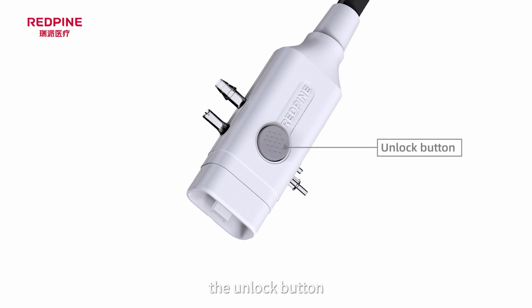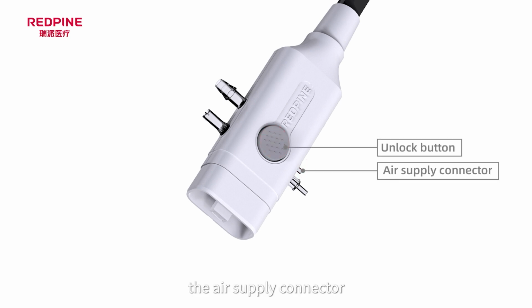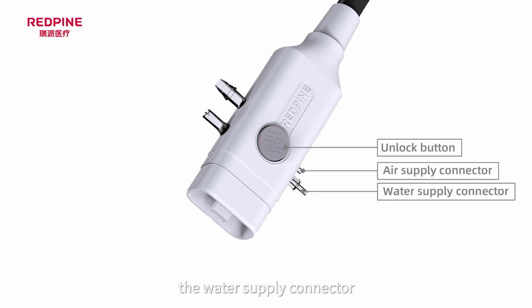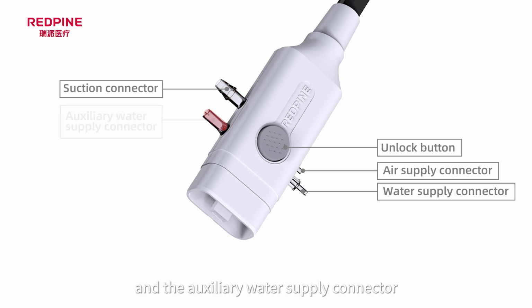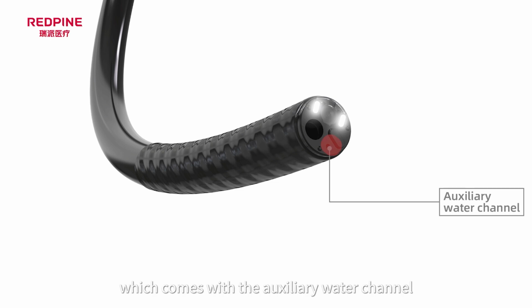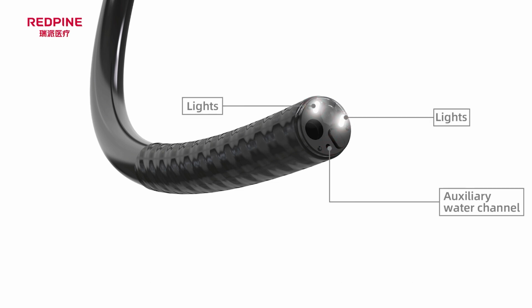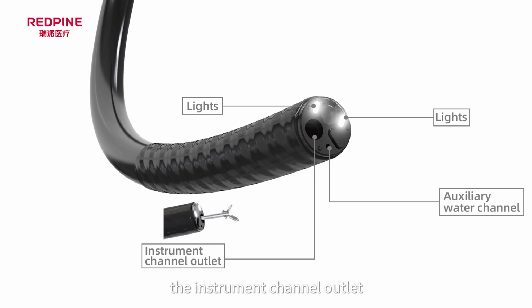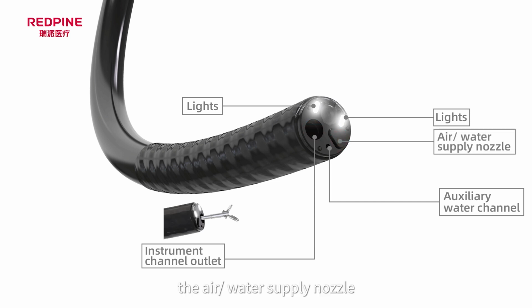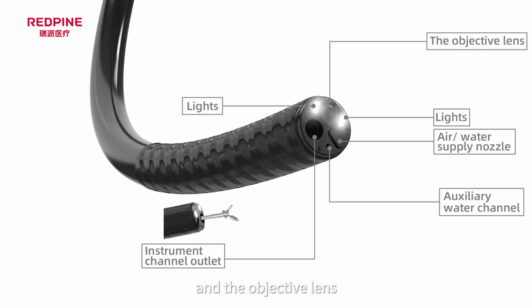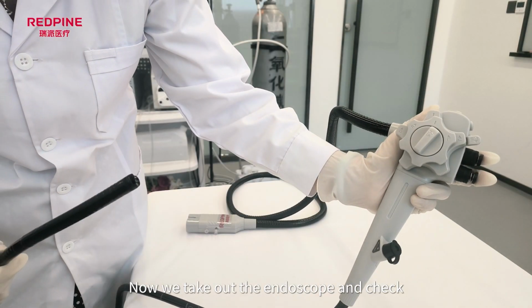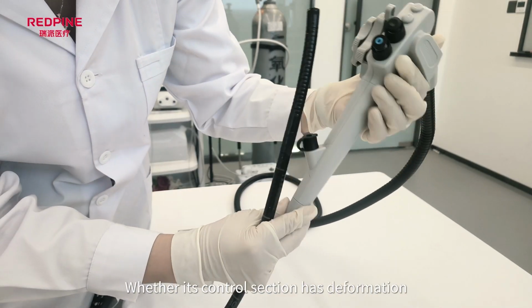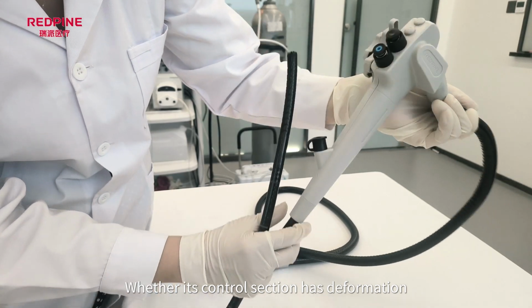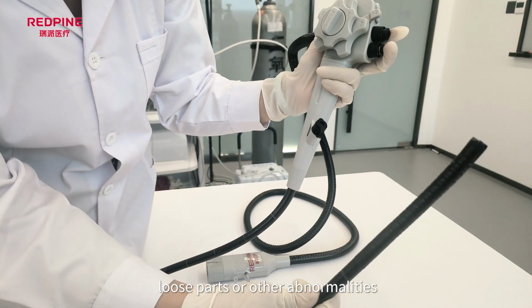The unlock button, the air supply connector, the water supply connector, the suction connector, and the auxiliary water supply connector, which comes with the auxiliary water channel. The lights, the instrument channel outlet, the air or water supply nozzle, and the objective lens. Now we take out the endoscope and check whether its control section has deformation, loose parts, or other abnormalities.